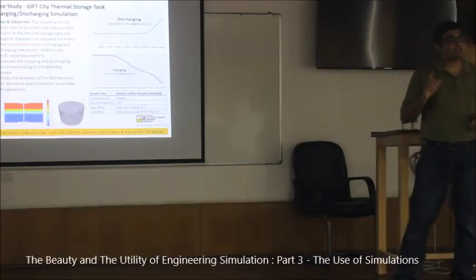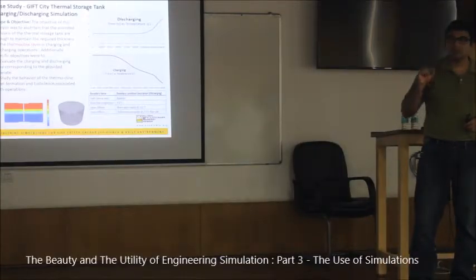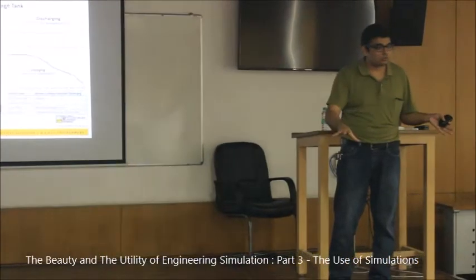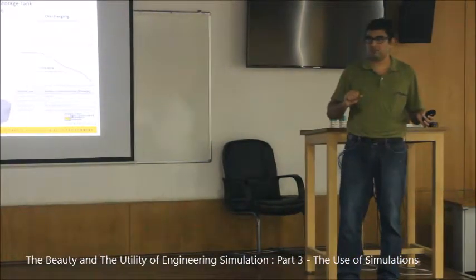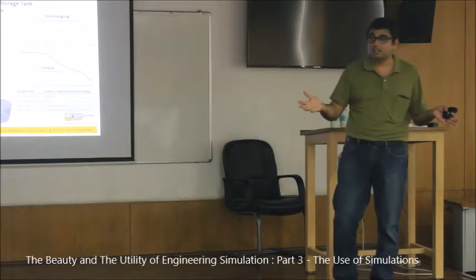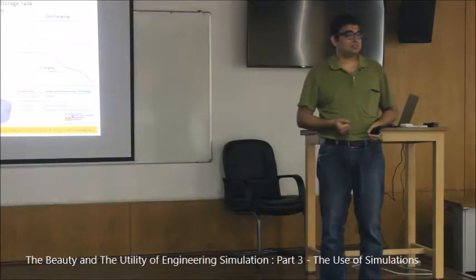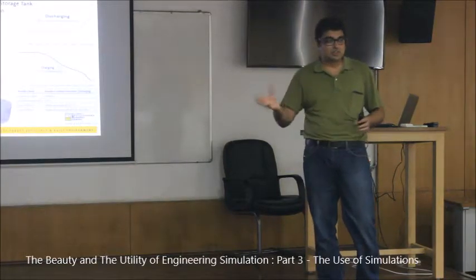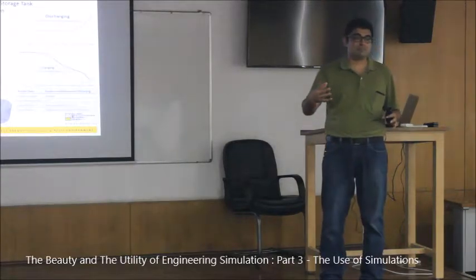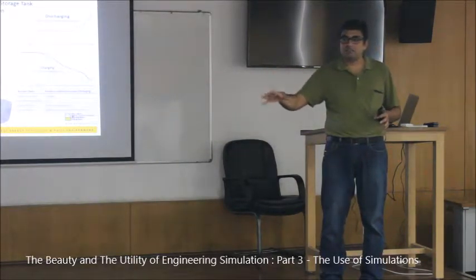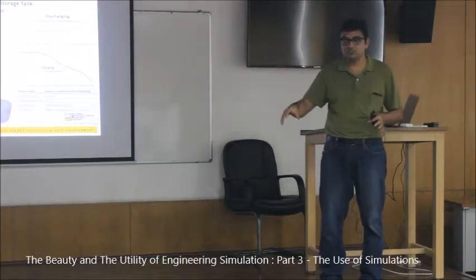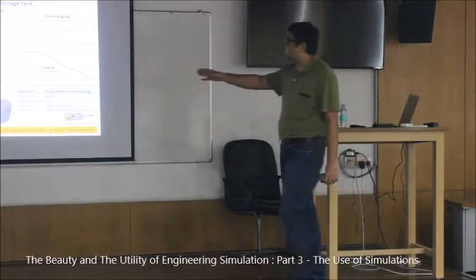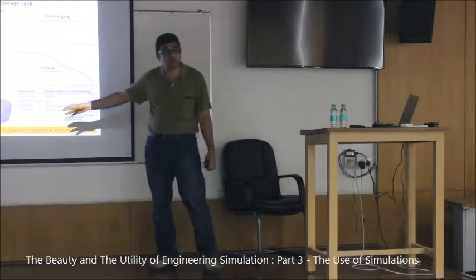Now imagine this, that the night tariff of the utility from where you are getting the electricity is lower than the day. And you have to use your building in the day itself. What would you do? So you tend to store the chilled water. Storing the chilled water would make sure that in the night time it is stored, cooled to a certain level. And in the daytime, chillers are off and you're using it. So this is a heat storage, a cold storage kind of thing.